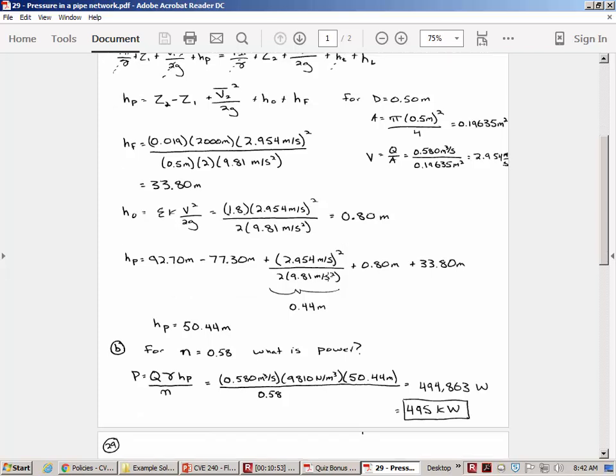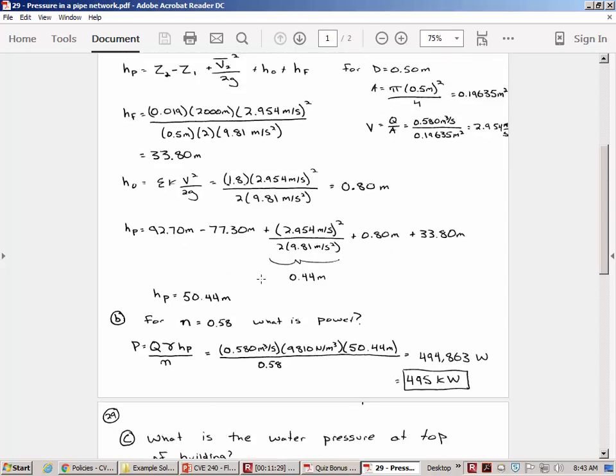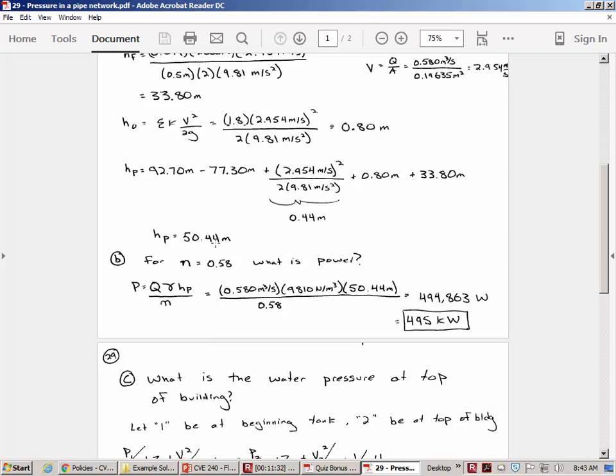So if we substitute everything together, you can see that here's the elevation difference between the two points. The pump definitely has to add at least that much head, the head required to physically lift the water. But then it also has to add enough head to overcome the losses, and enough head for the velocity head at 2. Velocity heads are relatively small. You can see it's only 0.44 meters of head due to the velocity. The majority of the energy that has to be added by the pump is to lift the water, the elevation difference, and the friction losses. So all together, we have the 50.4 meters of pump head, and then you can see for the efficiency factor, that works out to about 495 kilowatts.